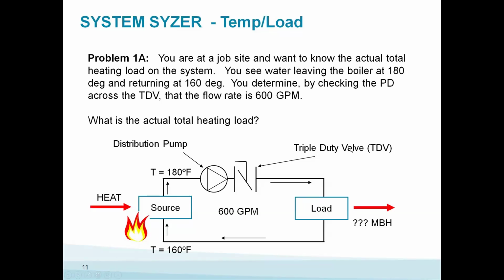And when I look at the pressure differential gauges across a TDV, we talked about that last week, a multi-purpose valve, in this case, a triple duty valve on the discharge of the pump. So we've got some ports and we're looking at these gauges. We determined that the pump's pumping 600 gallons a minute. So the question is, at that given moment, at that snapshot, 600 GPM, 180 coming out, leaving, and 160 coming back, what's the plant load under? What is it operating at?